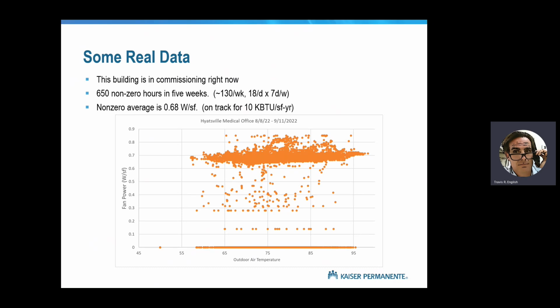If the building does not need to be occupied, don't fall for that. We actually fell for that in the early days. We had an engineer and a commissioning guy say, oh, this building really needs to be occupied and have some load in it before it'll start working according to the design. Words to the wise, do not fall for that. This building right here is using 3 to 4 times the fan power compared to its design, and bringing people into the building is never going to help that problem, right?